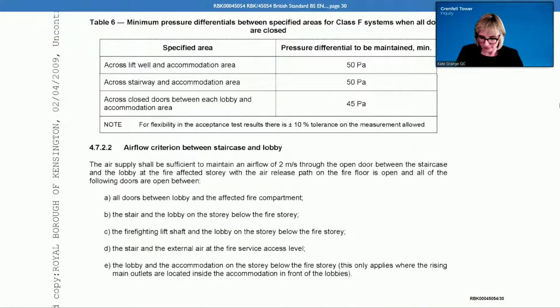Right. I think I can see where the important reading, or the reading we're interested in, is the flow rate across the door to the staircase. So that's the reading you would take. The second column is the reading you would take. The other doors being open, you don't take any readings. They're open so that you've got flow coming from other areas. And what you're trying to do is make sure that the 2 meters a second is maintained whilst you've got other leakage paths. But you don't measure those leakage paths because they're not of importance for the value. The value we're interested in is the staircase door value.